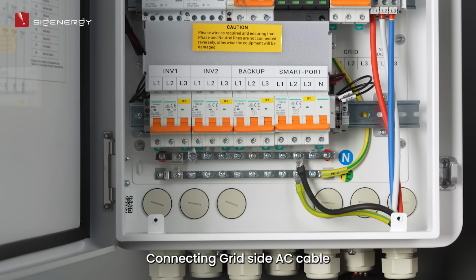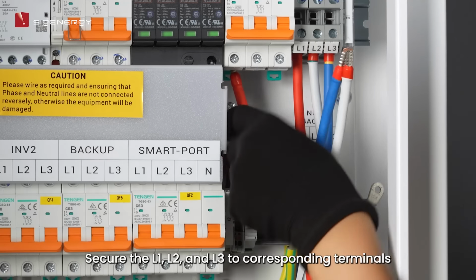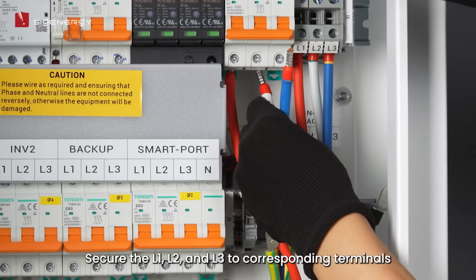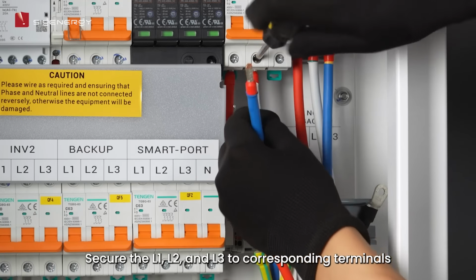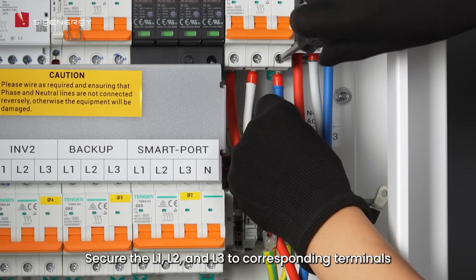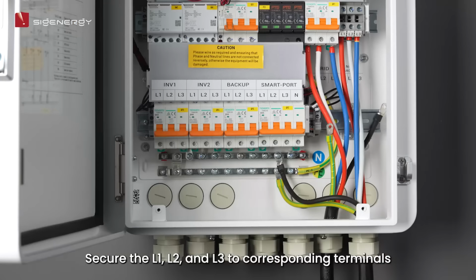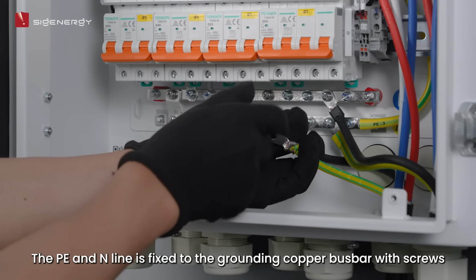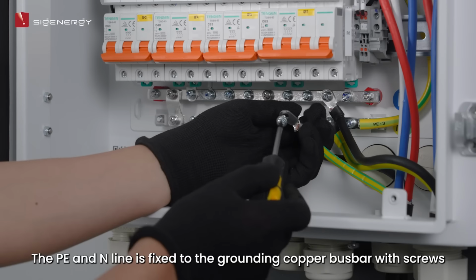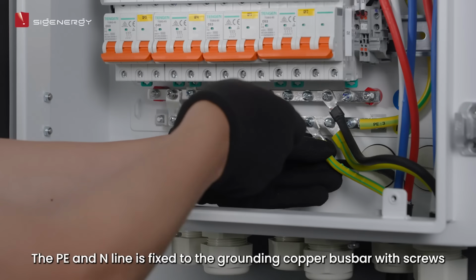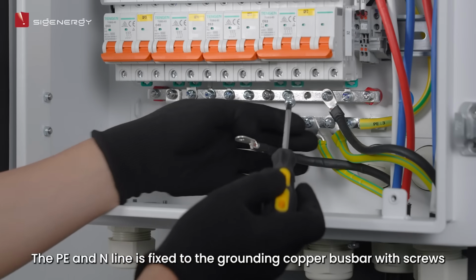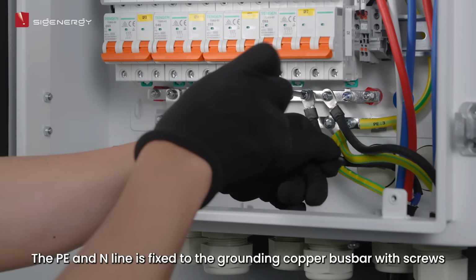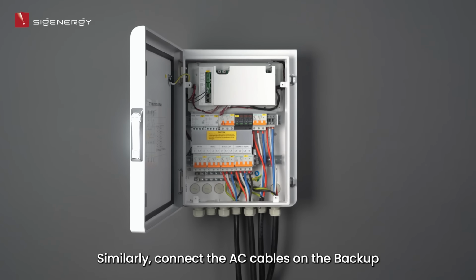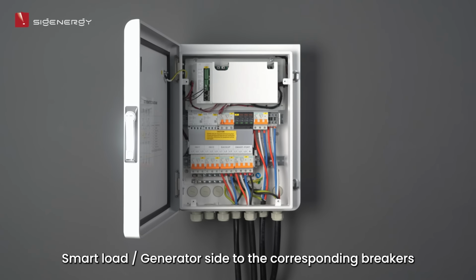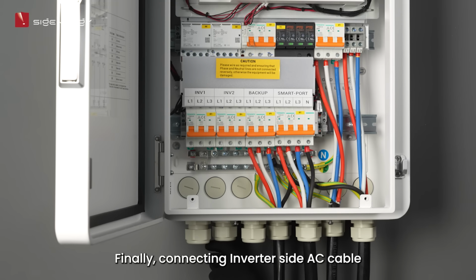Connecting grid side AC cable. Secure the L1, L2, and L3 to corresponding terminals. The PE and N line is fixed to the grounding copper bus bar with screws. Similarly, connect the AC cables on the backup, smart load, generator side to the corresponding breakers. Finally, connecting inverter side AC cable.